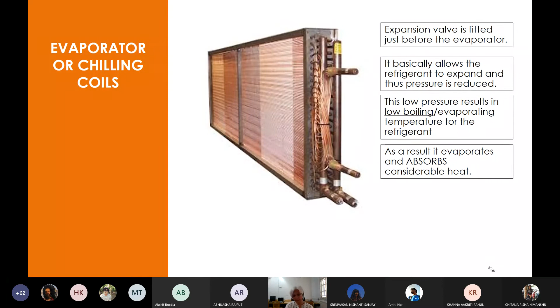If this is an air system, then the name of the system is the direct expansion system. If you are taking heat from water, then you are chilling the water. In that case, the system's name will be chilled water system. So now you have two main centralized systems that we'll be studying: in one you are cooling the entire building using chilled water, and in the other you are using chilled air to cool the building. So these are the two centralized systems.